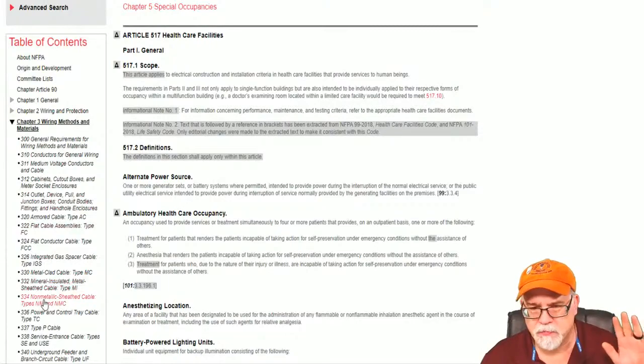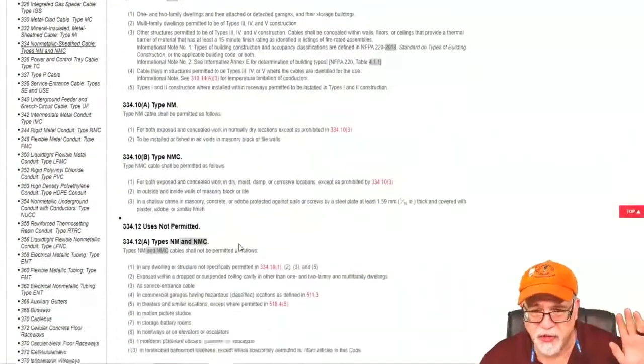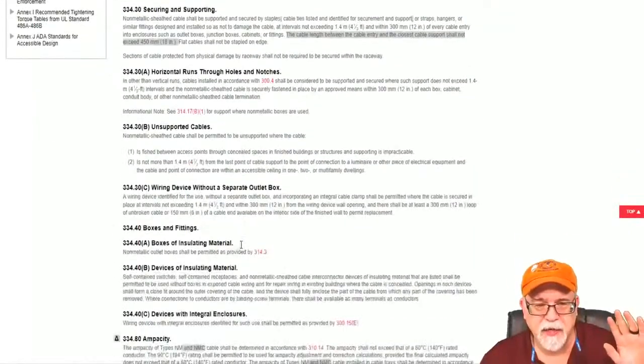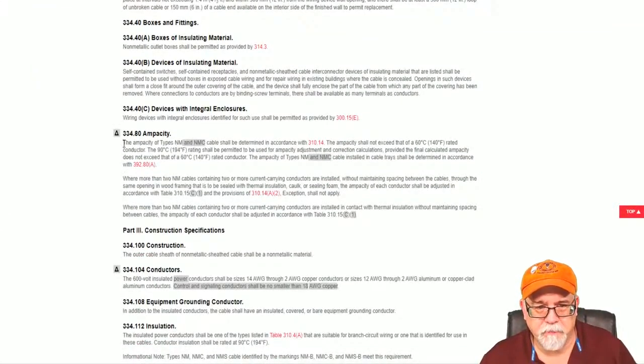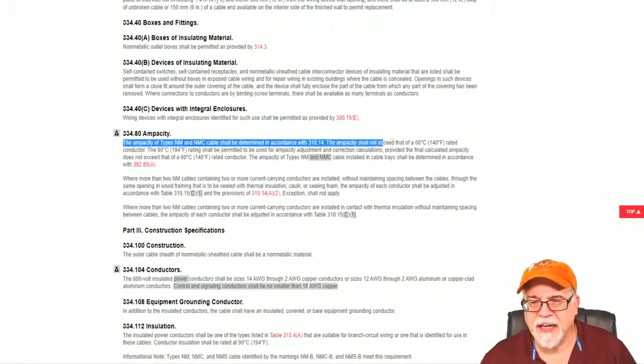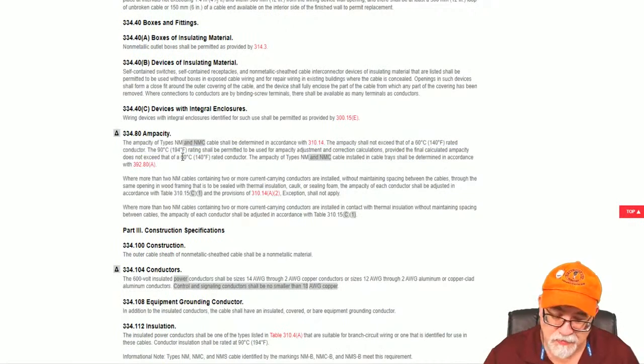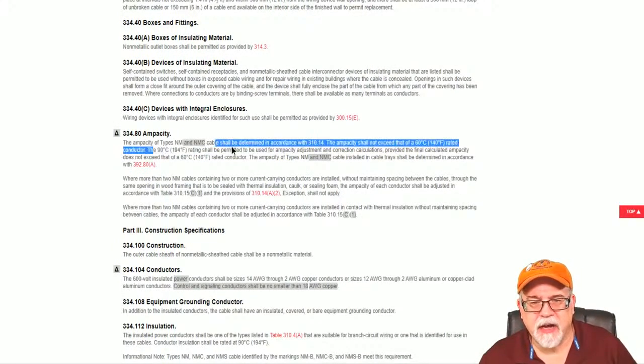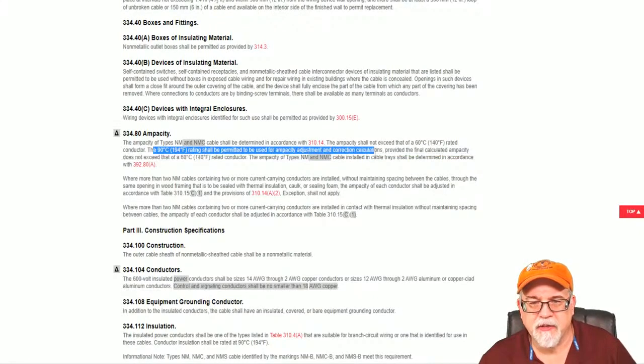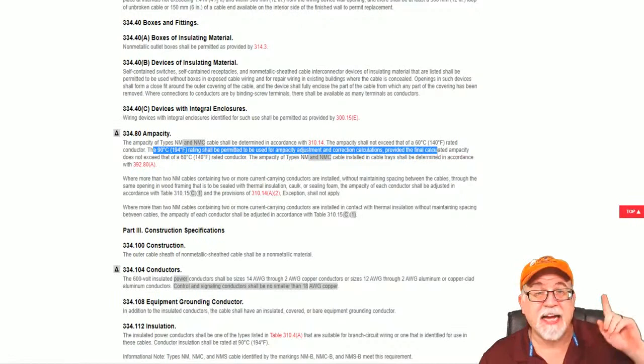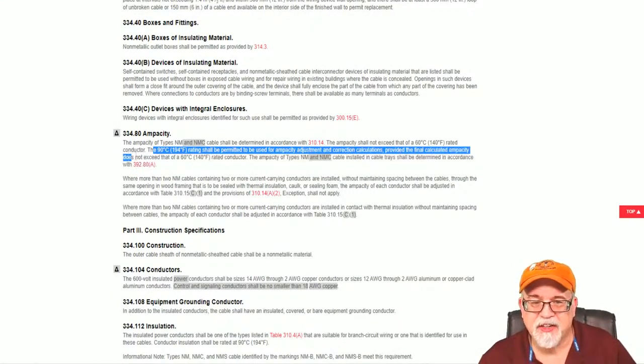We're at Article 334, okay? So I want to go to 334 just to talk about something, let you see, okay? And ampacities. Now, ampacity of type NM or NMC shall be determined in accordance with 310.14. The ampacity shall not exceed 60 degrees C rated conductors. Okay? So, can't exceed the 60. The 90-degree rating shall be permitted to be used for ampacity adjustment and corrections calculations, provided that the final calculated ampacity does not exceed that of the 60 degrees C or 140 degrees F rated conductor.